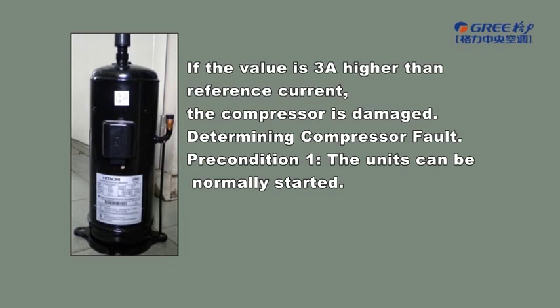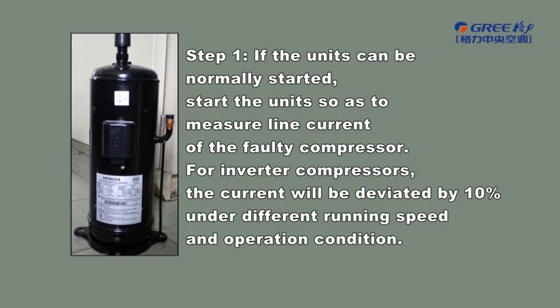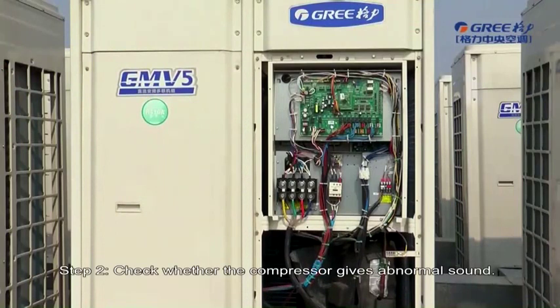Determining compressor fault. Pre-condition 1: the unit can be normally started. Step 1: if the unit can be normally started, start the unit so as to measure the line current of the faulty compressor. For inverter compressors, the current will be deviated by 10% under different running speeds and operation conditions. Step 2: check whether the compressor gives abnormal sound.